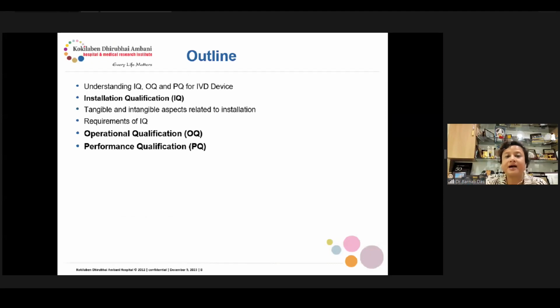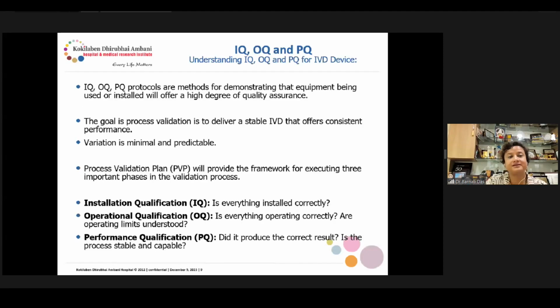I remember when I started my journey in lab, initially we were only bothered about the performance qualification in lab. About IQ, about OQ, we used to think whoever the manufacturer or whoever the IVD person supplying us the instrument or kit, they will do the IQ, OQ, PQ. So why should I bother? I should only be bothered about the part of PQ, the performance qualification. But that's not correct. From installation qualification to operational qualification and performance qualification, we as lab personnel need to validate that, verify that, and we need to sign that. So let's see how to do that.